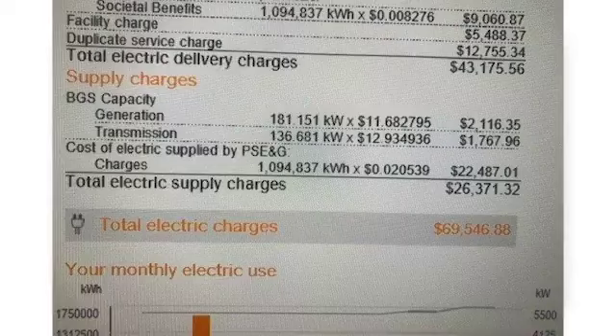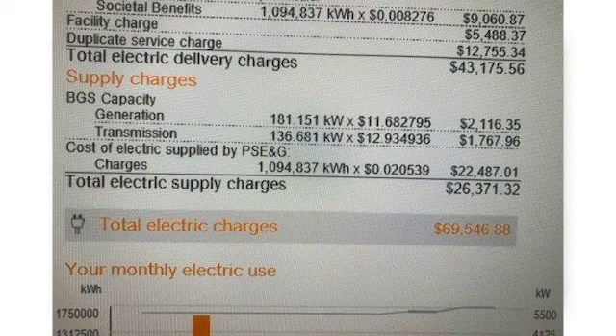Okay, let's take me to one more shot here of the monthly demand charges, and this is probably the most important thing that we do. When you look at these monthly charges, you'll see that this is actually based on last year's presence to grid. So you'll see here, scores in the hundreds of kilowatts, a couple of 100, 150 kilowatts, for both the generation and the transmission. And each one of those has a monthly value of either $12 and change, or $11 and change, depending on which one it is. But the aggregate effect of these two charges together is $295 a kilowatt year. That's 1 kilowatt for 1 year. That's what you're spending for demand.